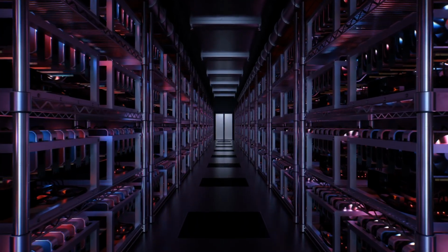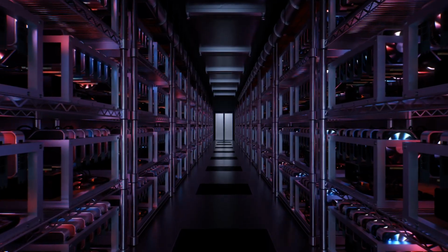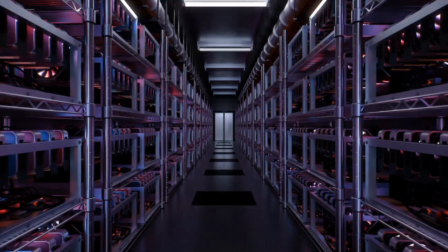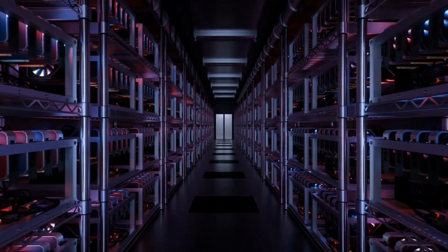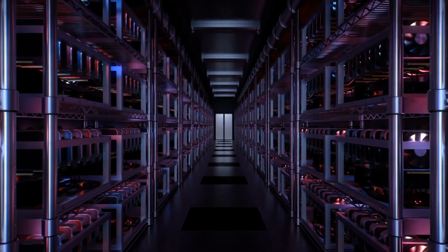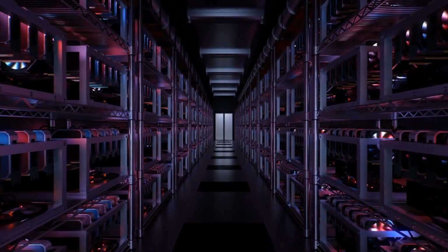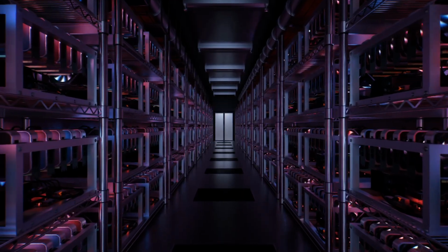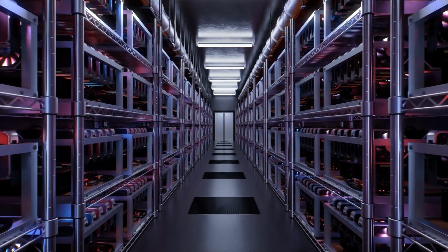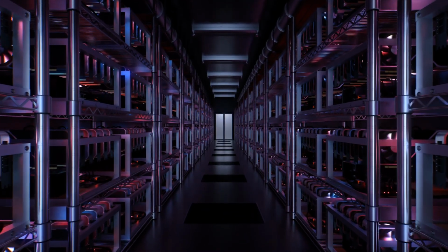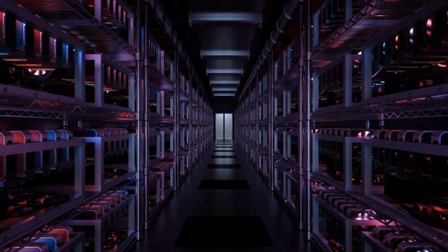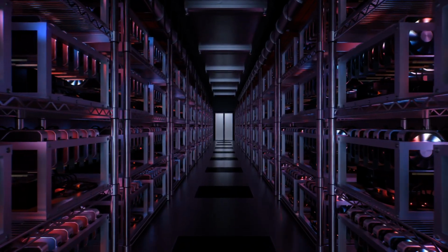Managing these two entirely separate, highly pressurized fluid loops, rushing up to 1,200 liters per minute, while handling microsecond pump failures, temperatures, and pressures, requires an incredibly sophisticated brain. You absolutely cannot manage this manually. You can't just flip a mechanical switch on the wall and walk away. A human cannot react fast enough to prevent a catastrophe here.